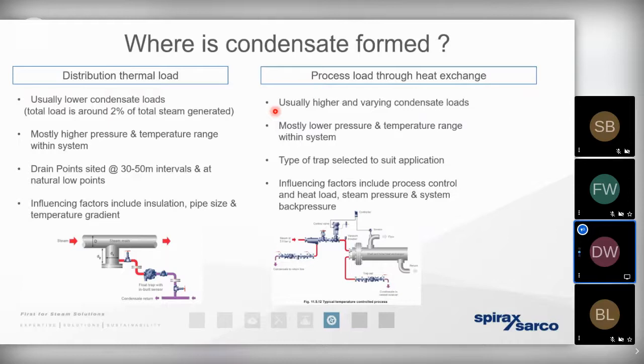If we undersize the steam traps, if we only size them on the running load, then we're exposing ourselves to the risk that that condensate is likely to back up and start to flood the distribution network. And it's at that point we get that erosion, corrosion, and water hammer that we spoke about. And the remainder of the condensate, well, that's going to be formed at the process. And that's a good thing because that's where we want the steam to give up its heat energy.